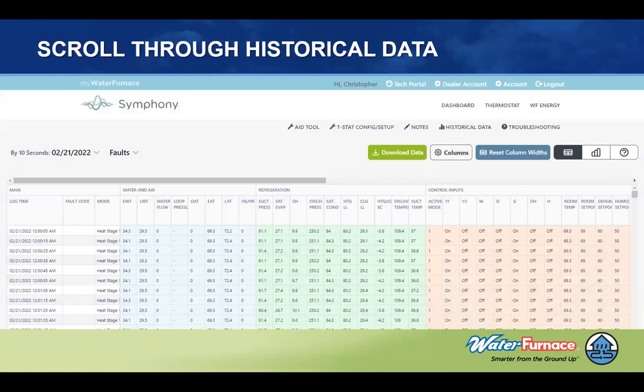So I wanted to show you the troubleshooting chart that we've had that shows the real time. We also have all of the parameters from the system that you can see in tabular form, that allows you to go to an exact time of day and look at where we're at. If you go to the fault at the top, it will take you directly to when the fault happened, and you can see what led up to that and what was going on. And as you learn the system and get more familiar with the inputs and outputs of the system, it becomes very easy to know how to service that piece of equipment.